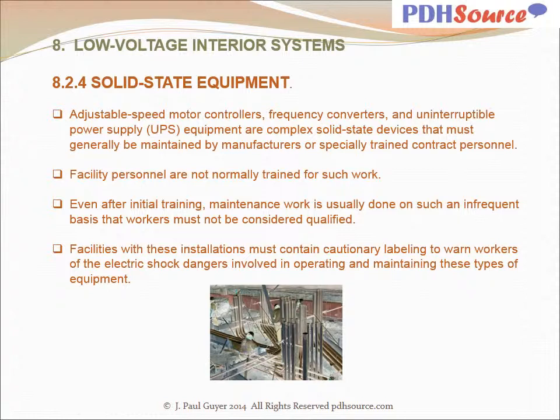With regard to solid-state equipment, adjustable speed motor controllers, frequency converters, and uninterruptible power supply (UPS) equipment are complex solid-state devices that must generally be maintained by manufacturers or specially trained contract personnel. Facility personnel are not normally trained for such work. Even after initial training, maintenance work is usually done on such an infrequent basis that workers must not be considered qualified. Facilities with these installations must contain cautionary labeling to warn workers of the electric shock dangers involved in operating and maintaining these types of equipment.